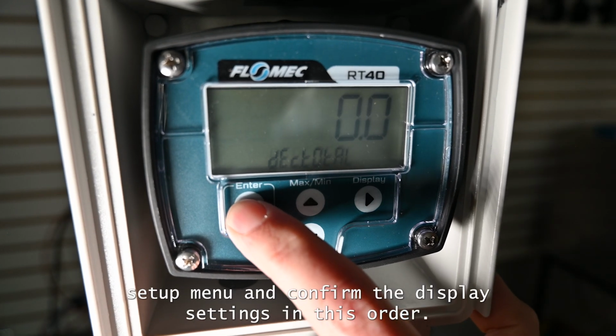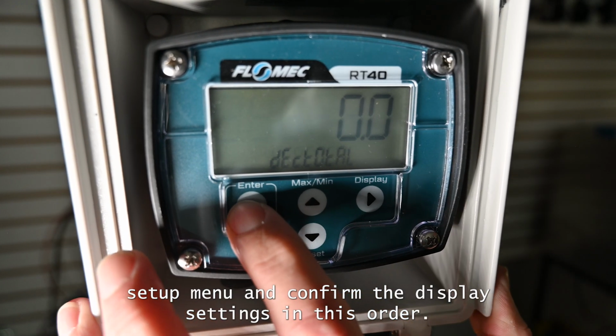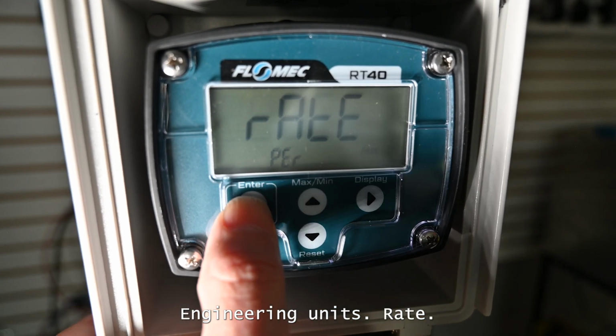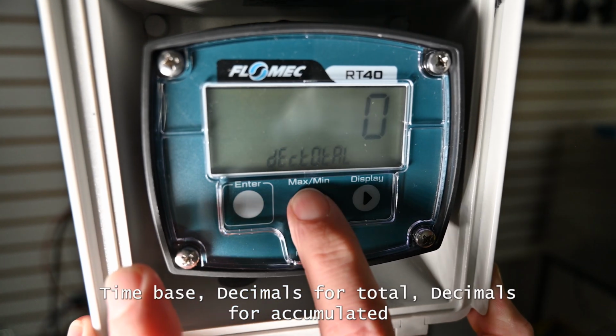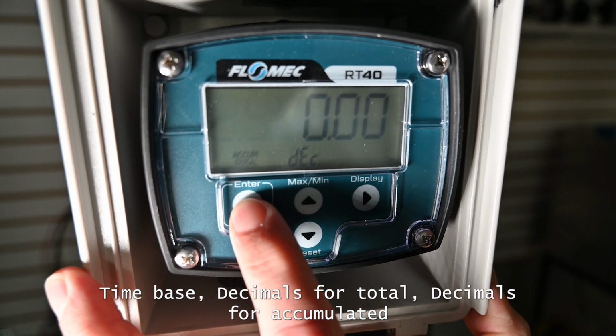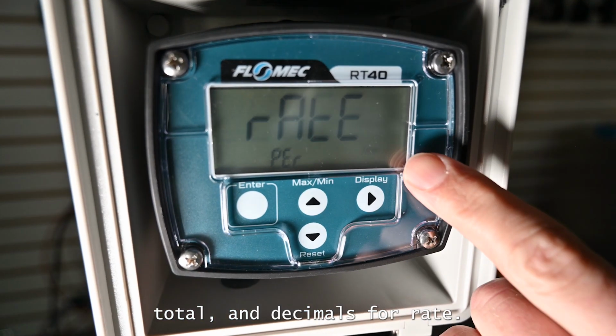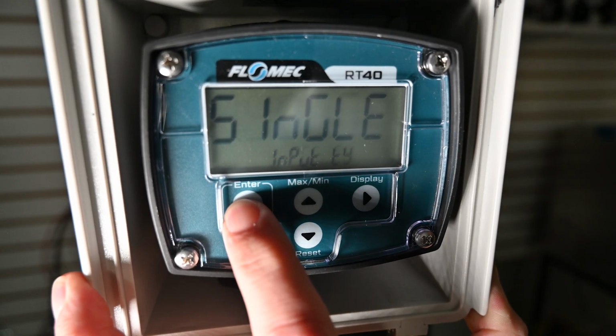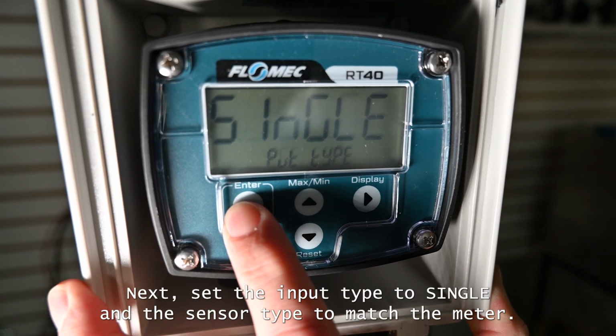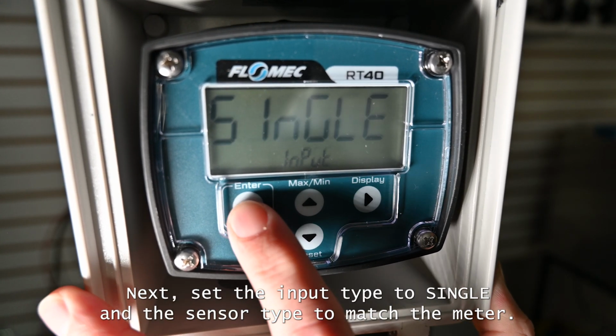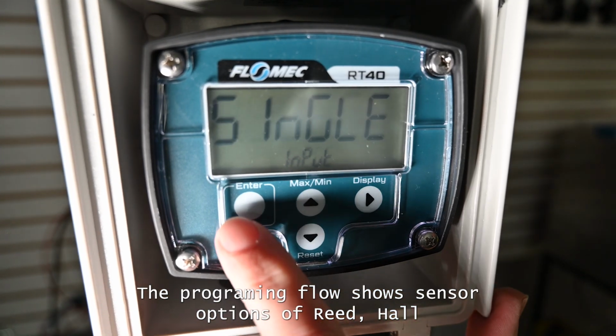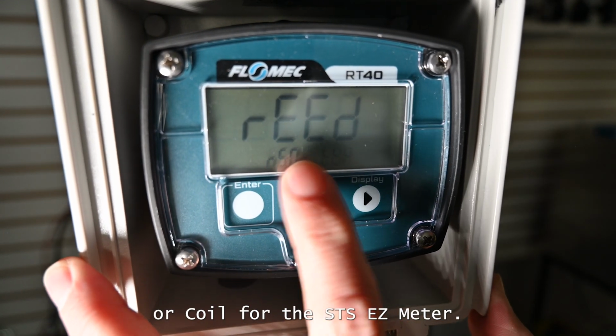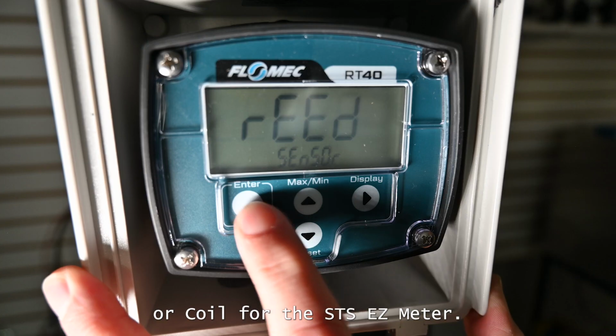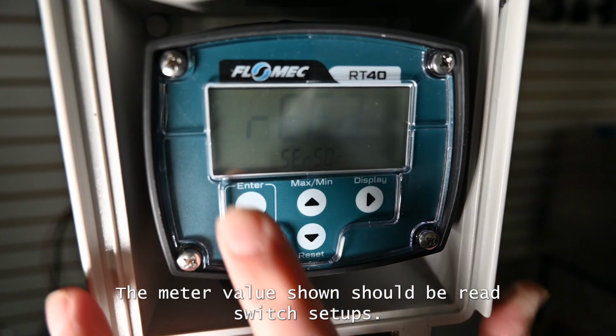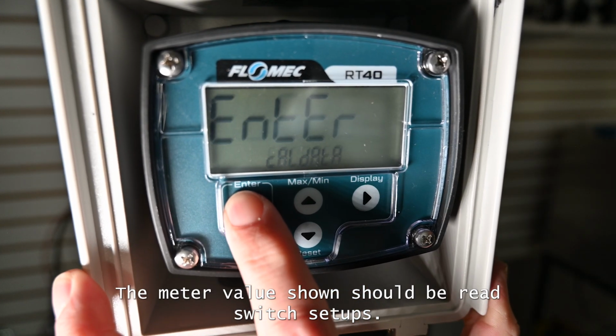Work through the setup menu and confirm the display settings in this order: engineering units, rate time base, decimals for total, decimals for accumulated total, and decimals for rate. Next, set the input type to single and the sensor type to match the meter. The programming flow shows sensor options of reed, Hall, or coil. For the STS EZ Meter, the meter values shown should be reed switch setups.